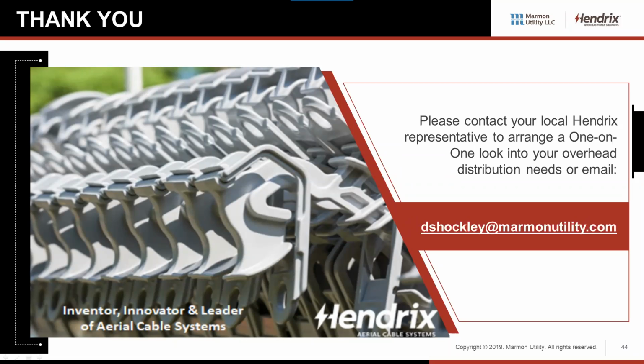But if you reach out to the manufacturers that do, a lot of them will say, we don't recommend you use it to support the weight of spacer cable. That being said, we've done a handful of projects from little tiny municipalities that will have a spacer cable circuit running from a substation to near their service center. And they use that for communications, to that large desert solar ranch in Southern California that uses OPGW.